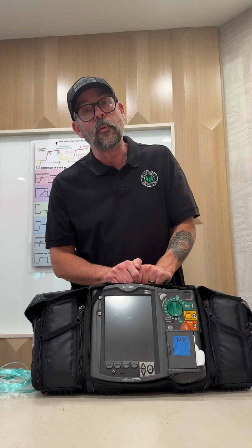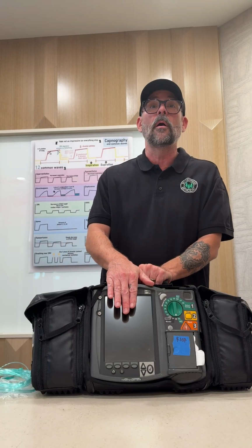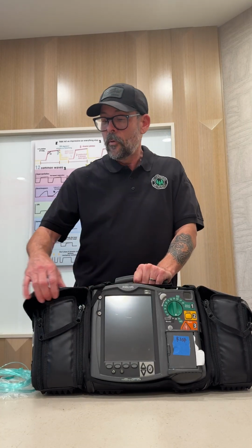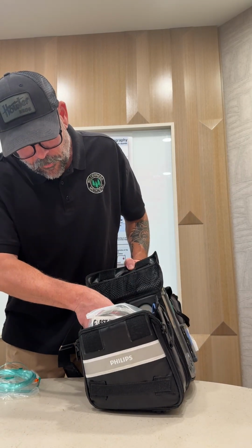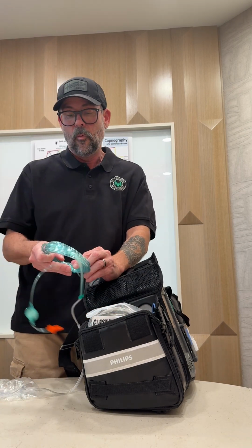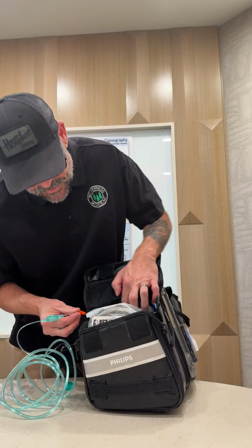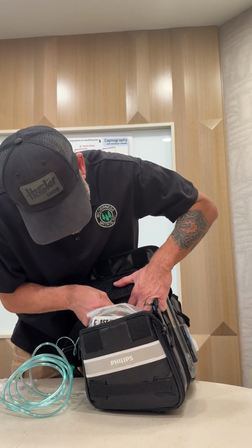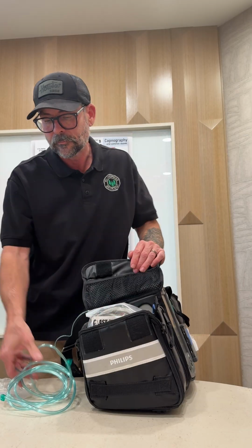So here at Wilderness, we have a couple of different types of capnography monitors. First and foremost, we have the one that's built into our cardiac monitors. You're going to need to locate the port where we attach our capnography monitor. On this particular unit, it is on the same side as the blood pressure cuff. There's a little trap door right here, and we push down to open that up. We find two little ports. Only one of them do we use, and that is the one that is darker in color.